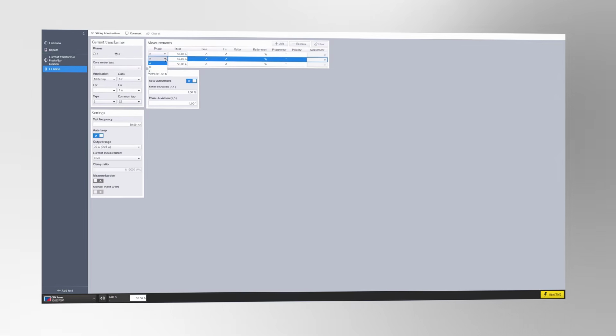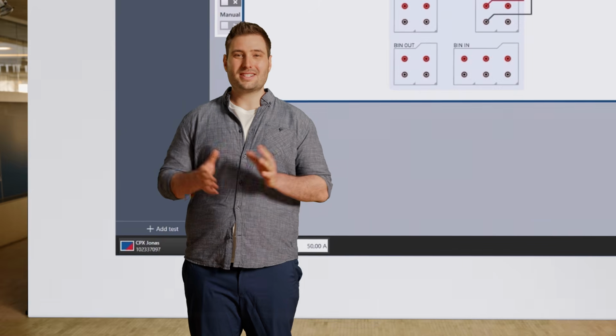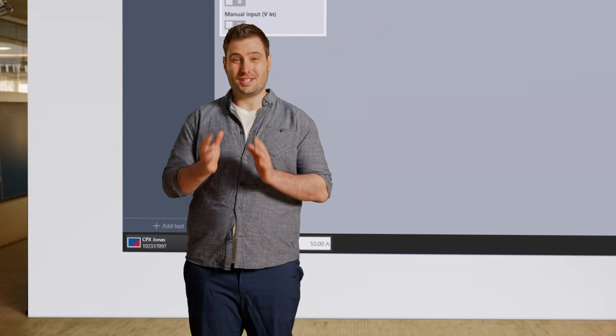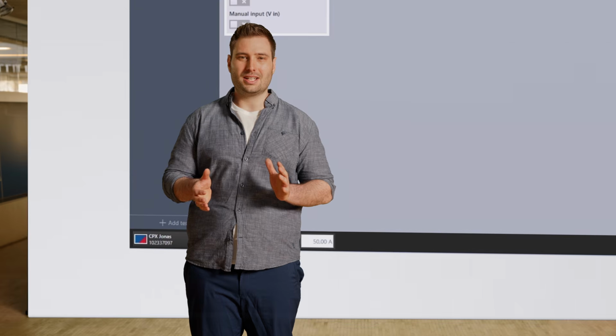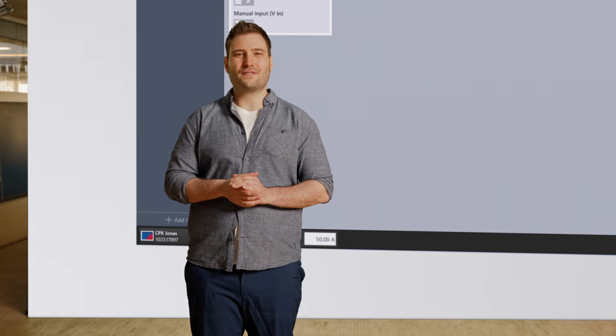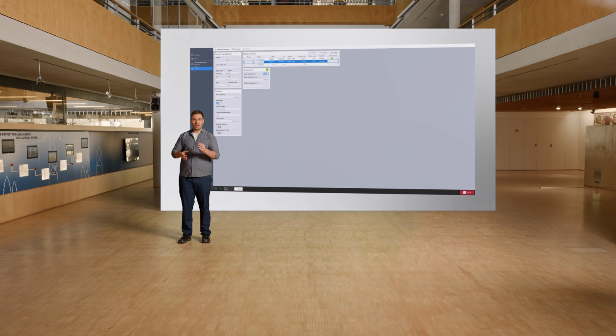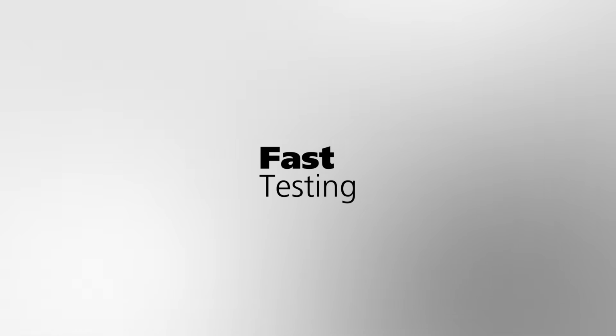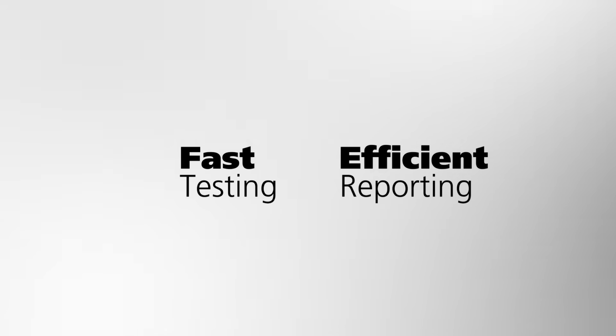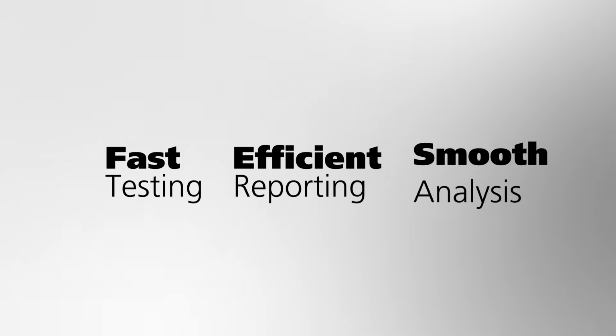CPXpert also helps you speed up your current transformer testing activities. For example, on-site, it's common to have 3 CTs, one per phase, lined up side by side. So far, this has resulted in multiple test documents, forcing you to open and close files repeatedly, scattering your test results across different views and making it harder to compare results efficiently. With CPXpert, you can test all 3 CTs in one unified view. This approach speeds up testing, makes reporting more efficient, and ensures smoother analysis than ever before.